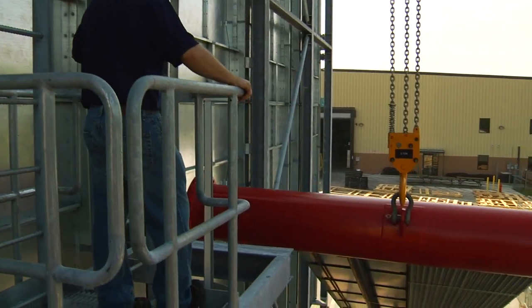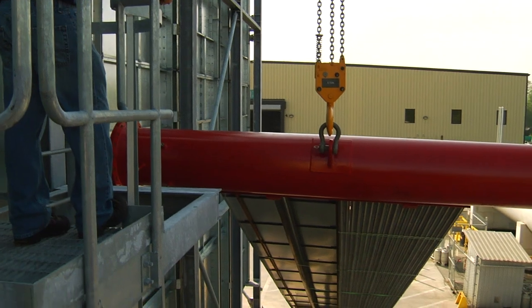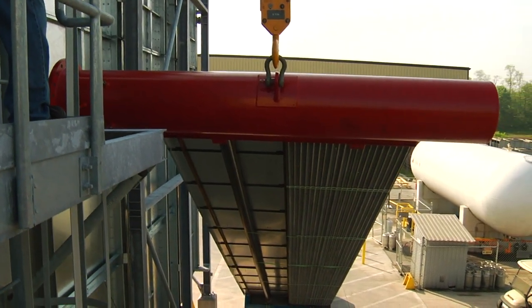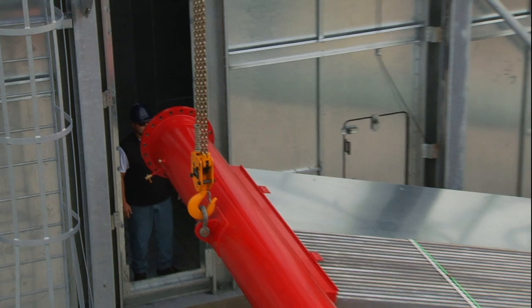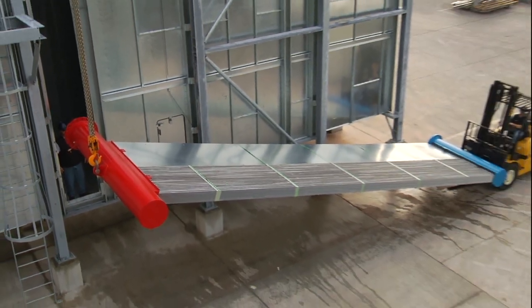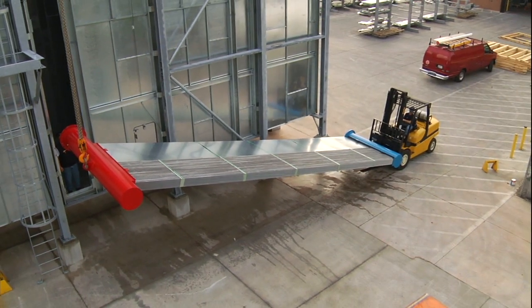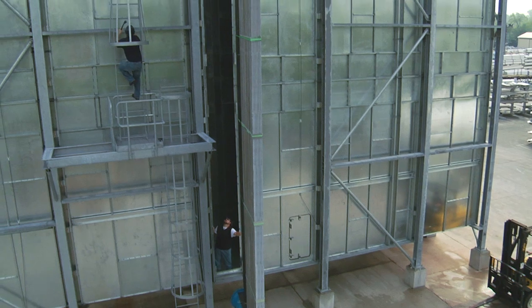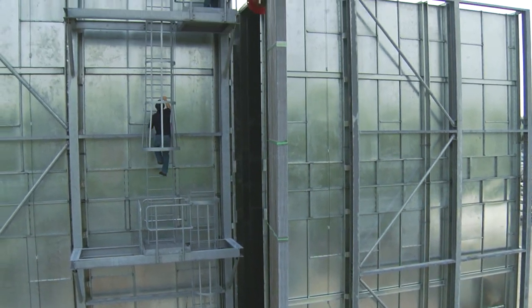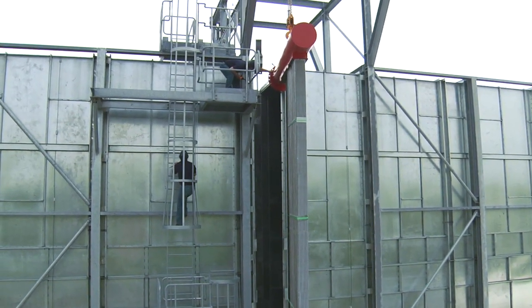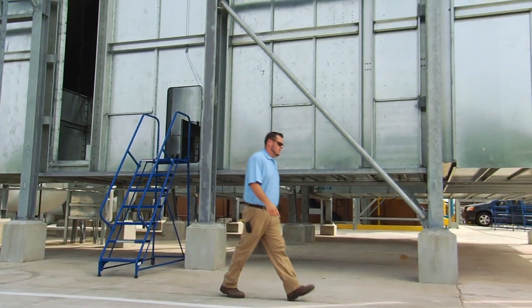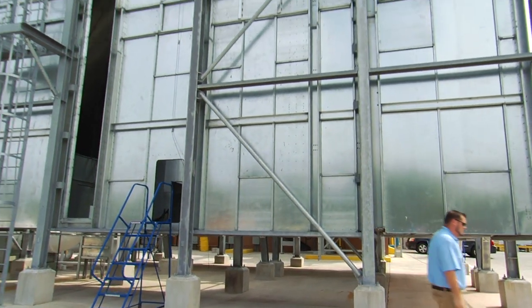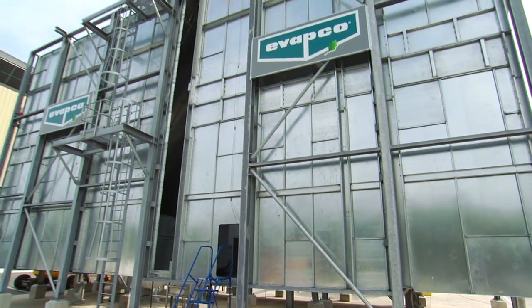Well, we want to test a full-sized air-cooled condenser tube bundle. So we've designed a facility that can accommodate an air-cooled condenser tube bundle that's 8 feet wide. 8 feet wide is a typical bundle width for shipping reasons. We designed it to be able to test one full-size bundle. In order to do that, it required that we build a wind tunnel test cell that's over 35 feet wide by 70 feet long, so it's quite a facility.